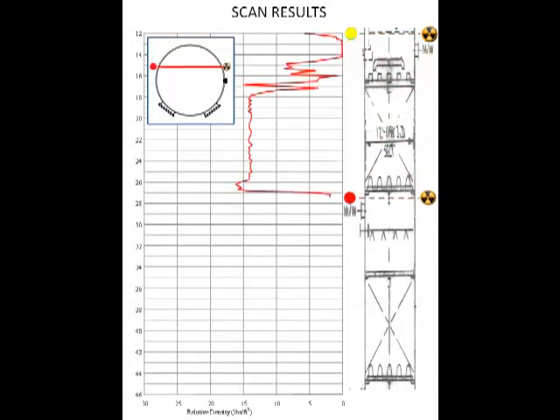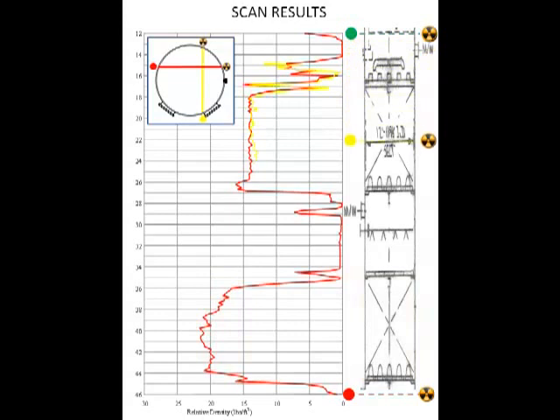As with each of the scans, a radioactive source and a detector are lowered down opposite sides of the tower to produce a density profile. Here we can see absorptions for the distributor, the upper packed bed, and the lower packed bed. The second scan shows a density profile similar to the first scan.